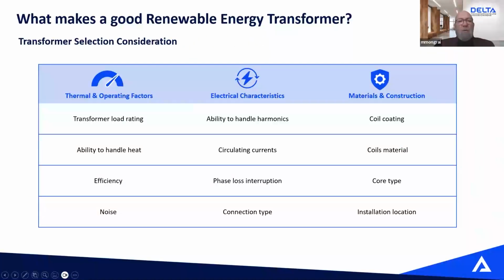So when you select the transformer, you have to figure out what your load rating is. What's the output of the inverter that I have to supply? What's the rating I need on my transformer? Do I keep a little buffer? Do I go full load? Usually, if you have a 300 kilowatt inverter, we recommend using a 300 kVA transformer, again because it's not fully loaded all the time. Then there's the ability to handle heat: you go from zero load to full load, with exposure to outdoor temperature, which in the summer can be very hot.